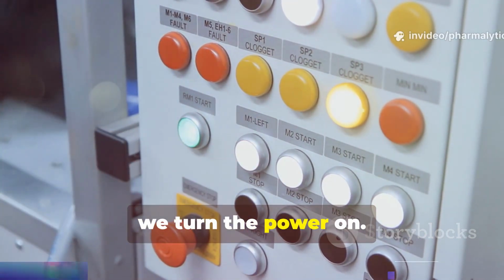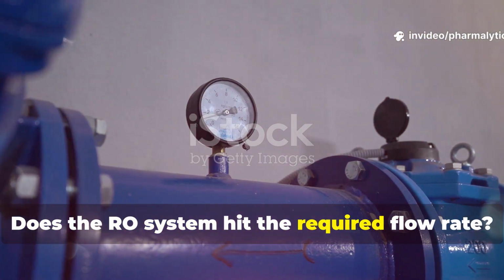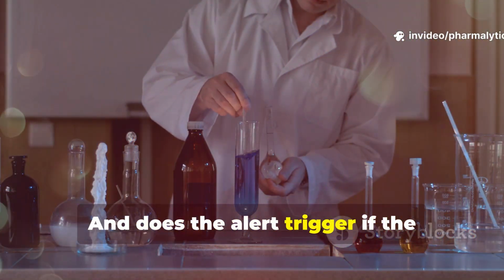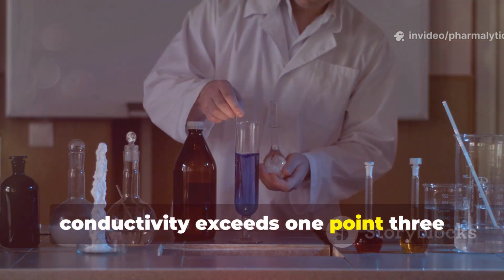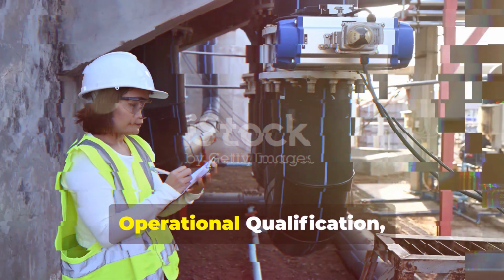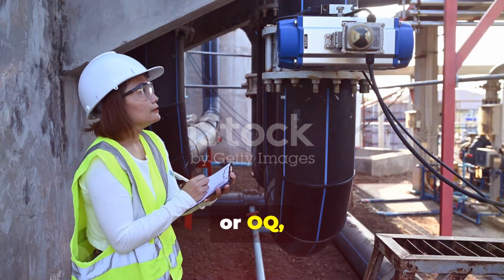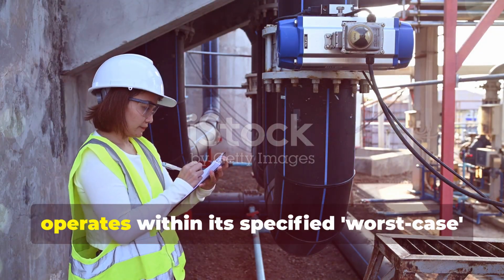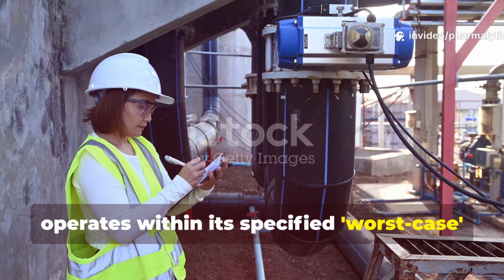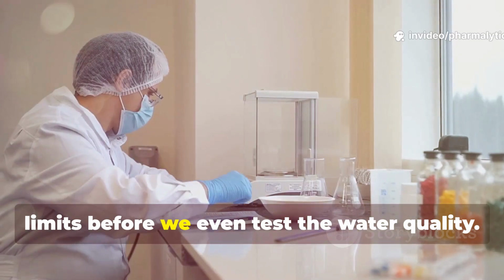Now, we turn the power on. Does the RO system hit the required flow rate? And does the alert trigger if the conductivity exceeds 1.3 microsiemens per centimeter? Operational qualification, or OQ, is all about proving the equipment operates within its specified, worst-case, limits, before we even test the water quality.